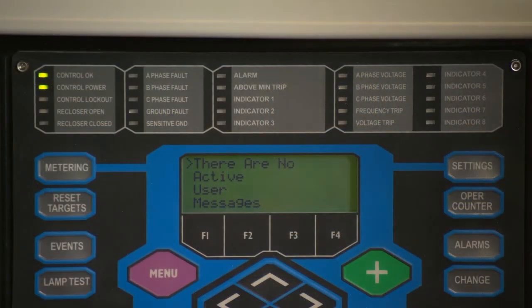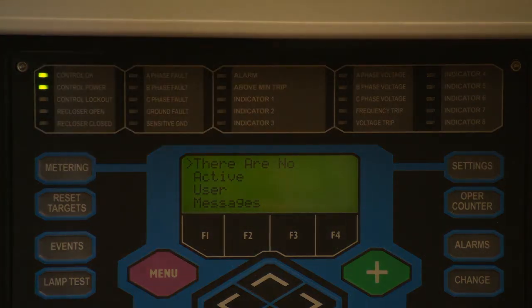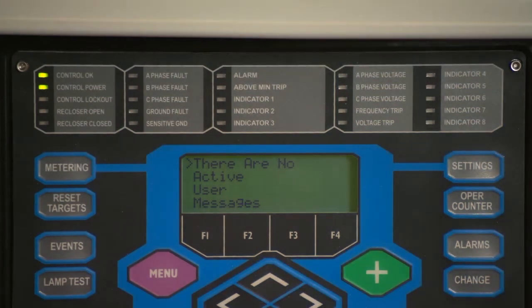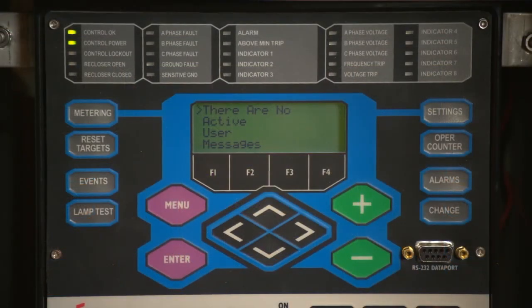When the phase or ground current exceeds its programmed minimum trip value and associated time current curve or TCC timing, the control initiates the programmed sequence of recloser tripping and reclosing operations via the CPU and RIF modules. If the fault is temporary, the control resets to the start of its operating sequence after a preset time delay. If the fault is permanent, the control performs its complete programmed sequence of reclose commands and locks out with the recloser open. Once locked out, the control must be closed via the operator panel or SCADA communications. This resets the control to the start of the operating sequence.